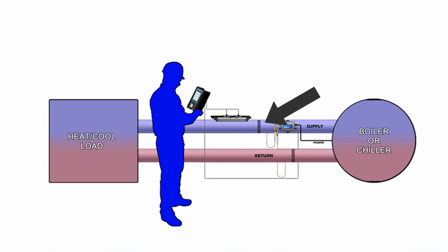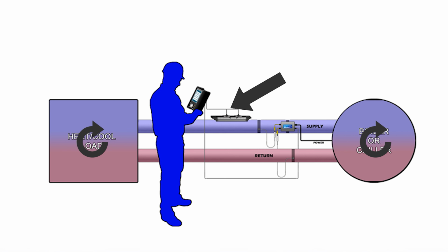Well then, clamp on an ultrasonic flow meter transducer to measure the flow of your hydronic supply. No need to measure the return because it's a closed loop. That's right, what goes out equals what comes back, hence 1 point of flow monitoring is usually sufficient.